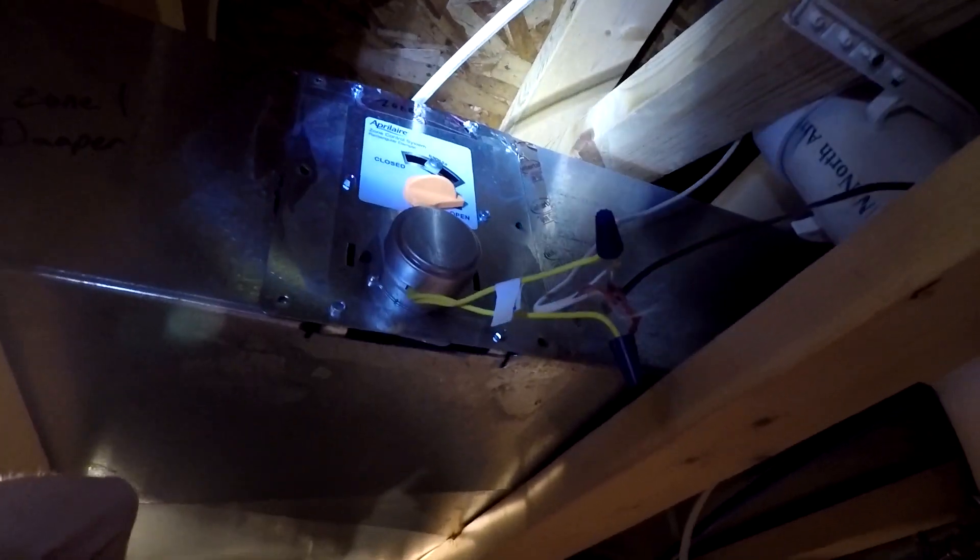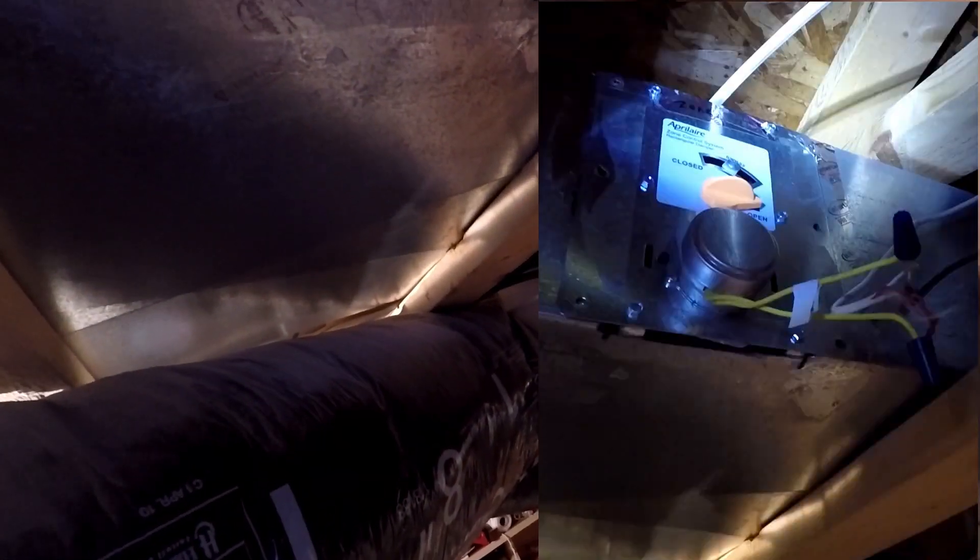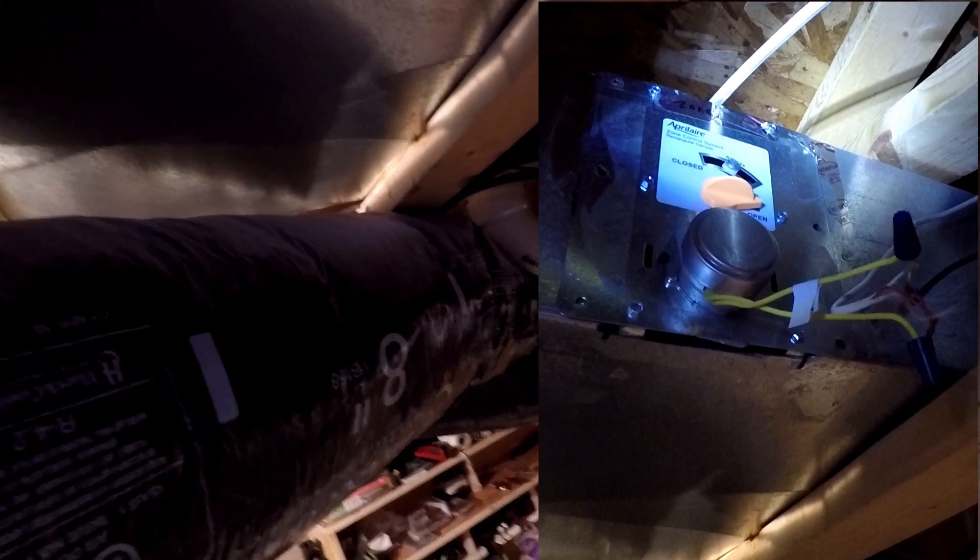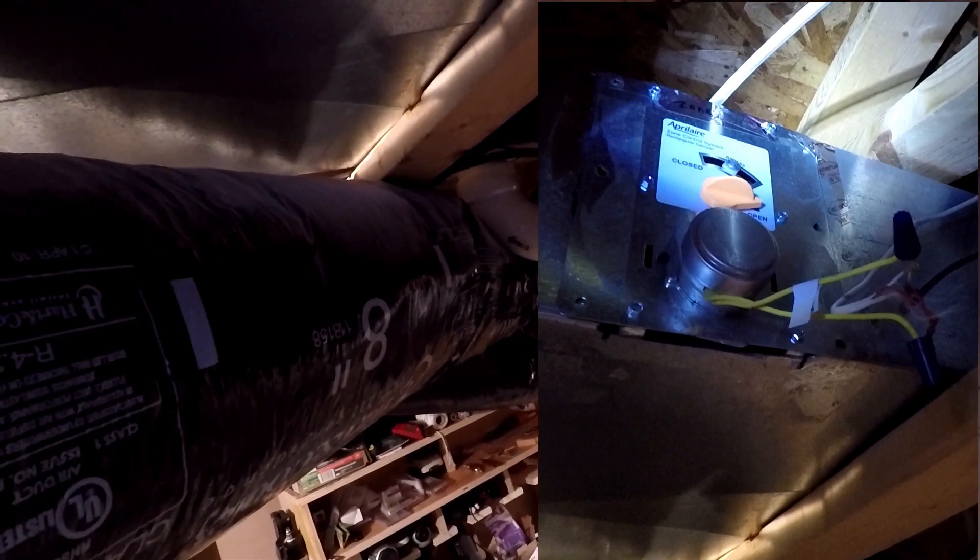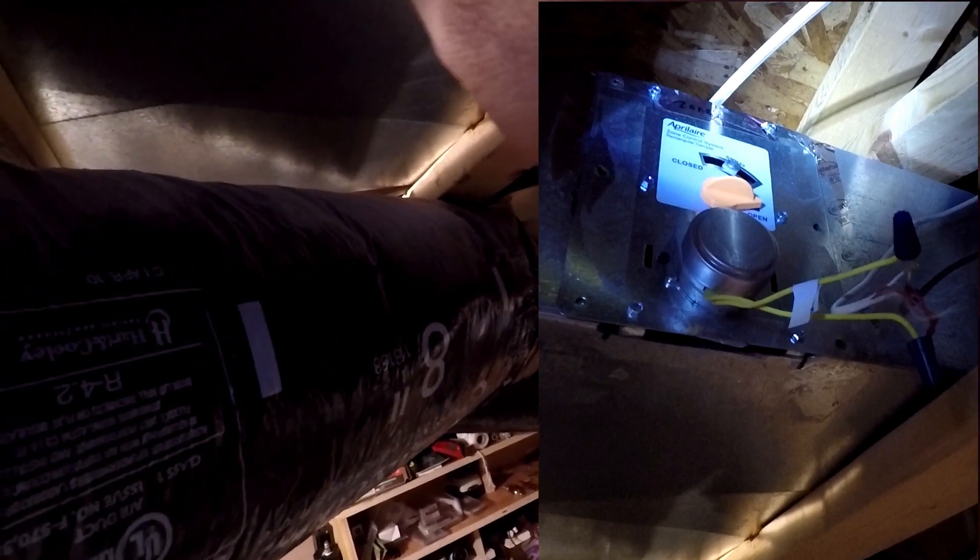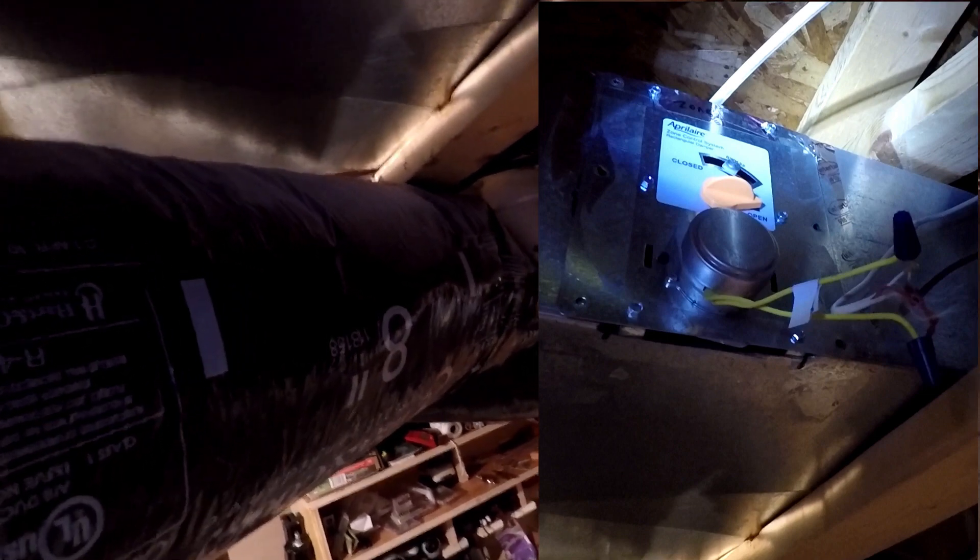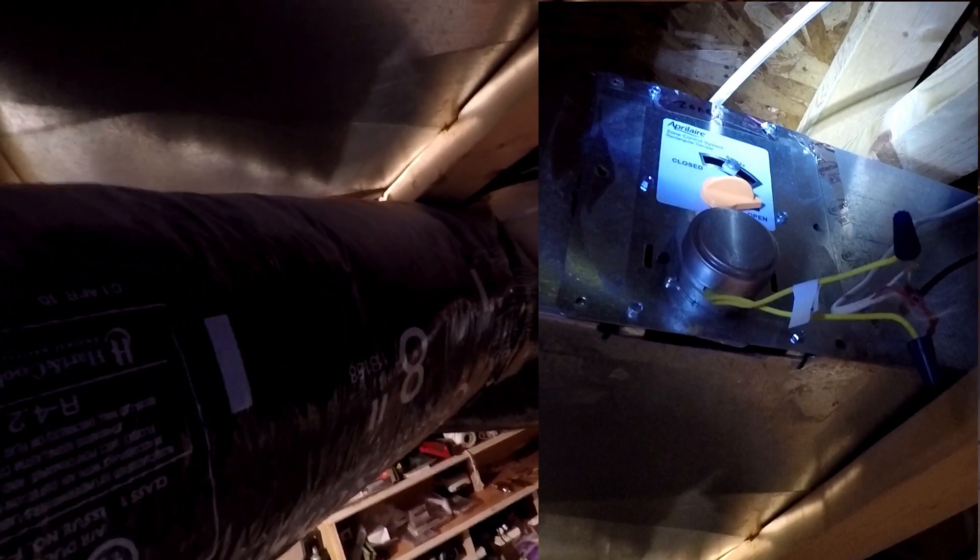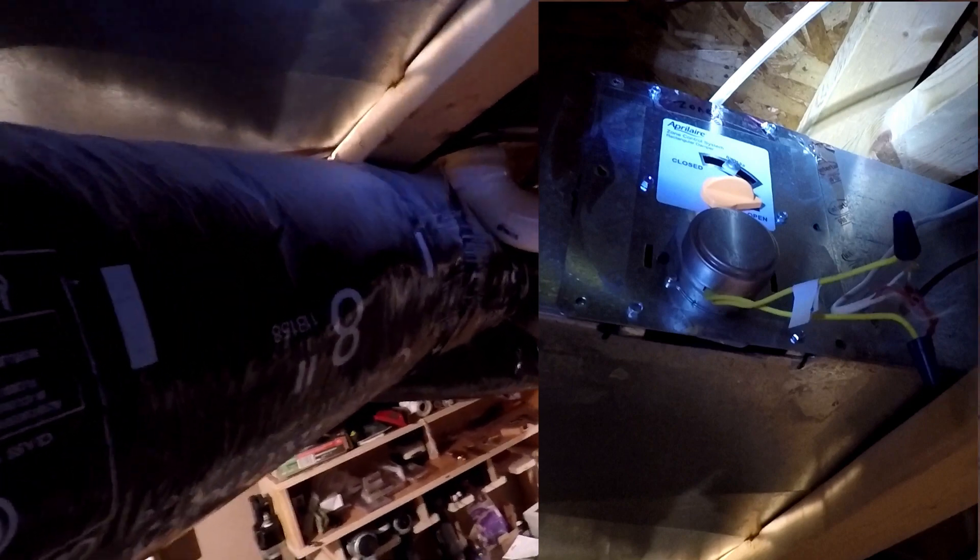Here's where the damper is located. Now even though there's supposed to be voltage coming to close this damper, it's open. There's a spring in here which opens it automatically whenever there's no power going to this. Yours should have six or four screws fixing it to the actual ductwork. I've taken those out already because I temporarily had this out and swapped over to another one. There should be some tape all around it to help seal the gaps.